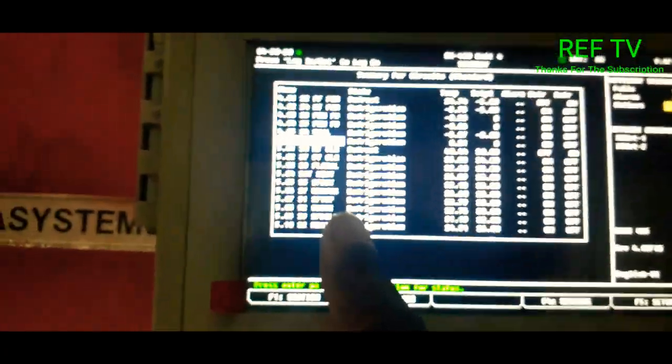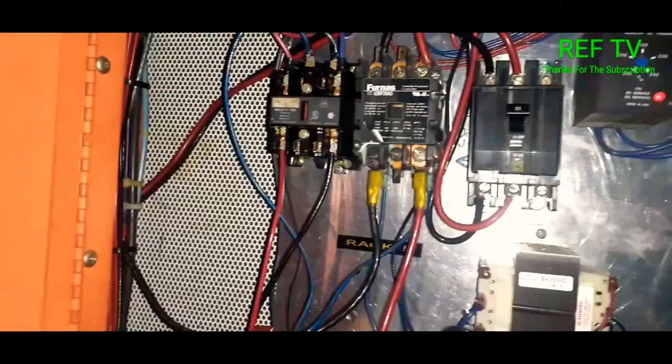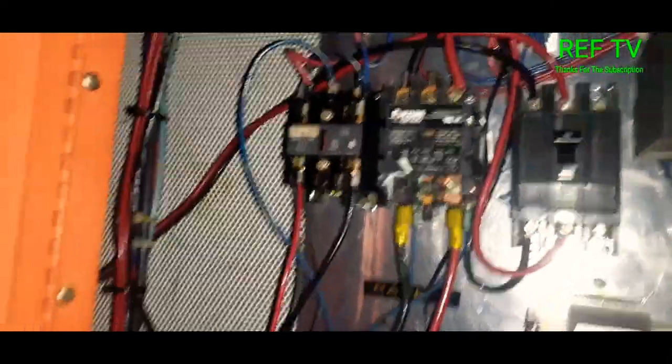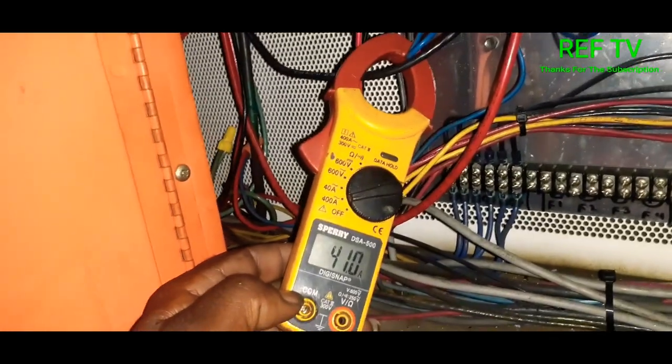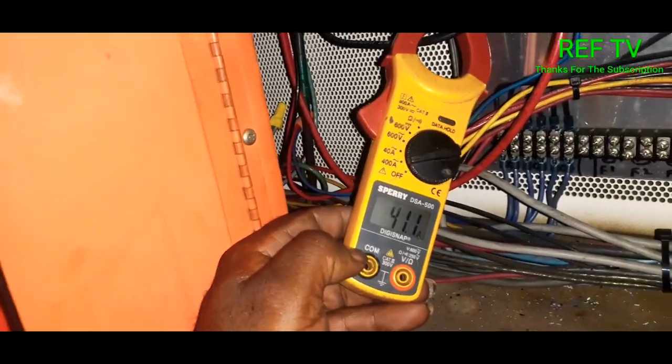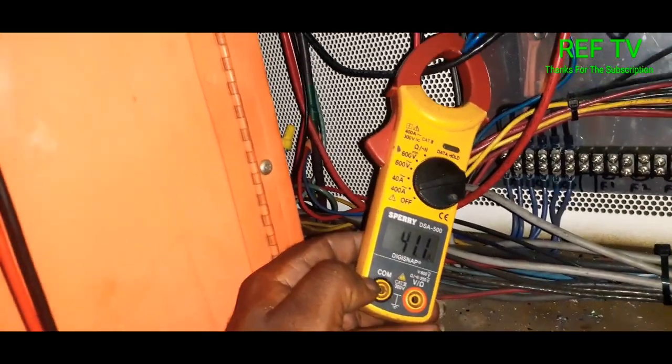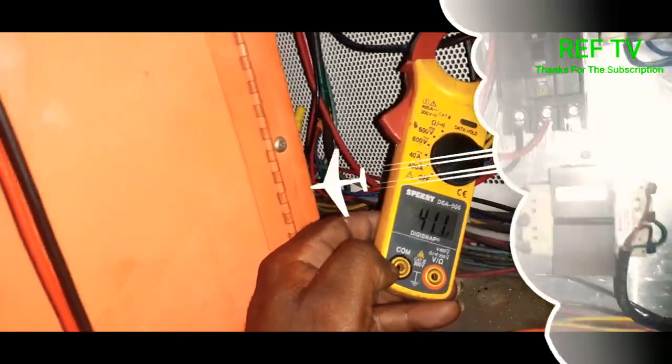All right, so we're back over here at our contactor. As you can see, our contactor is pulled in and we are drawing 40 amps. So our heaters are now working in our case. I'm gonna just let this thing go through and defrost. The heater wire is charged up here at the contactor from the connection.